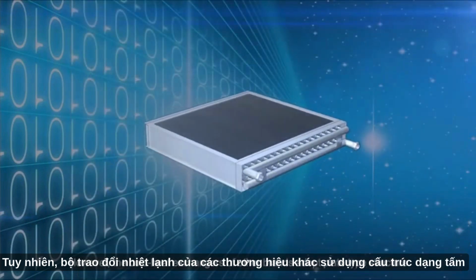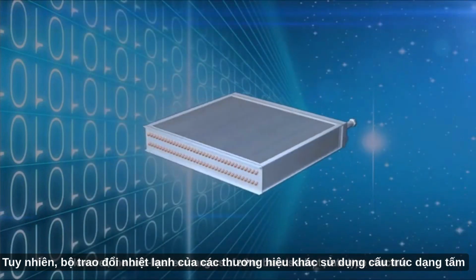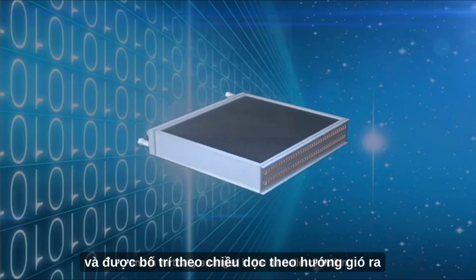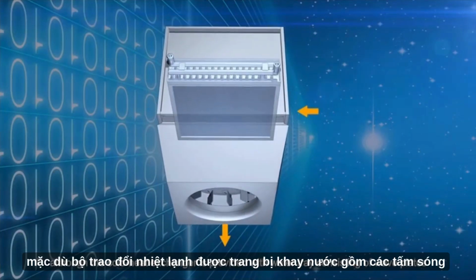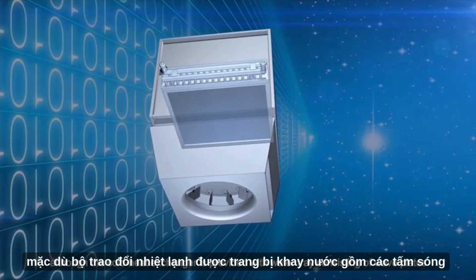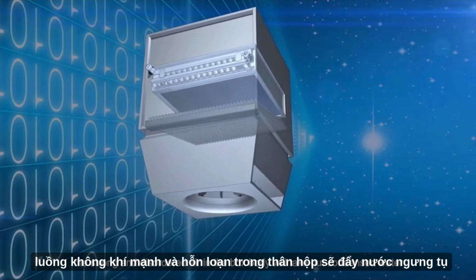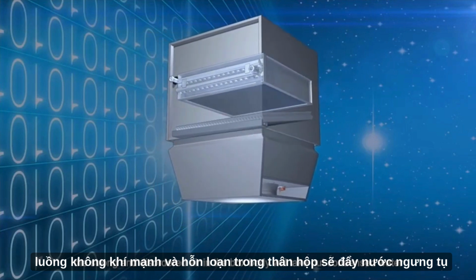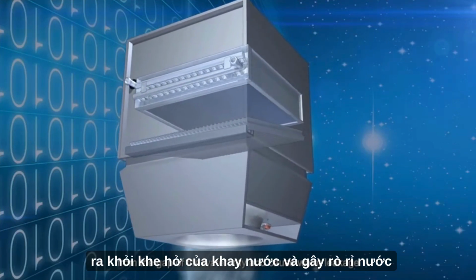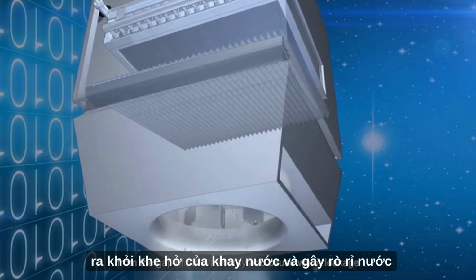However, the cold heat exchangers of other brands adopt plate-type structure and is vertically arranged in the air outlet direction. Although the cold heat exchanger is provided with water tray consisting of wave plates, the strong and disordered air in the box body will take out condensed water from the gap of the water tray and cause water leakage.